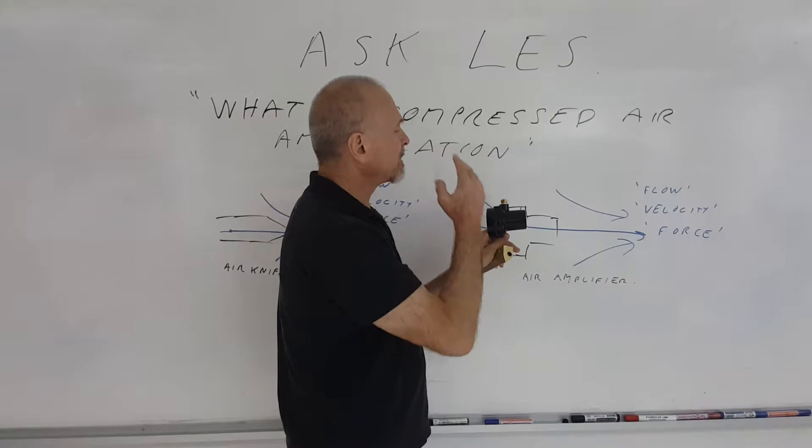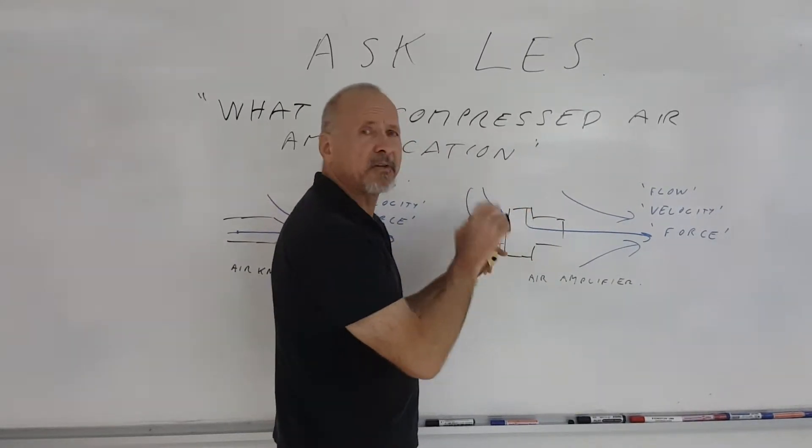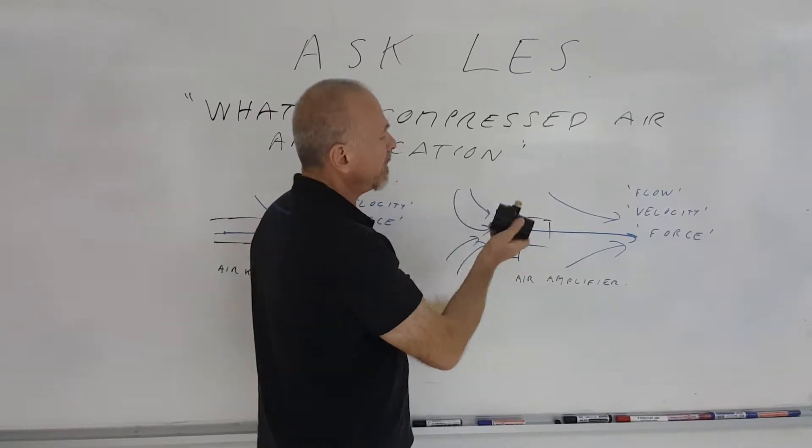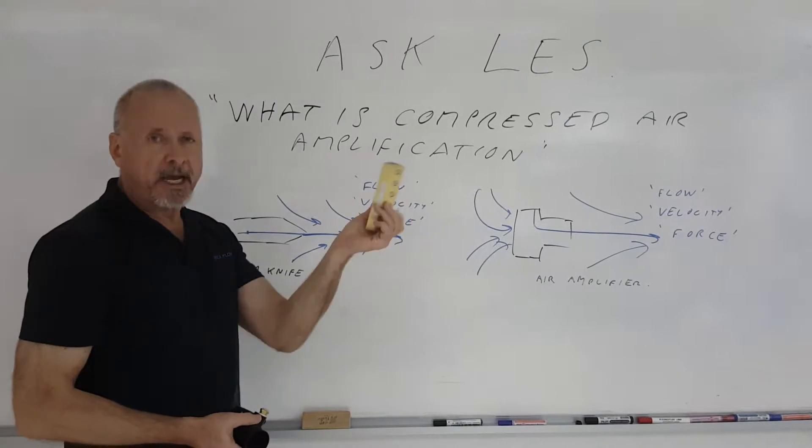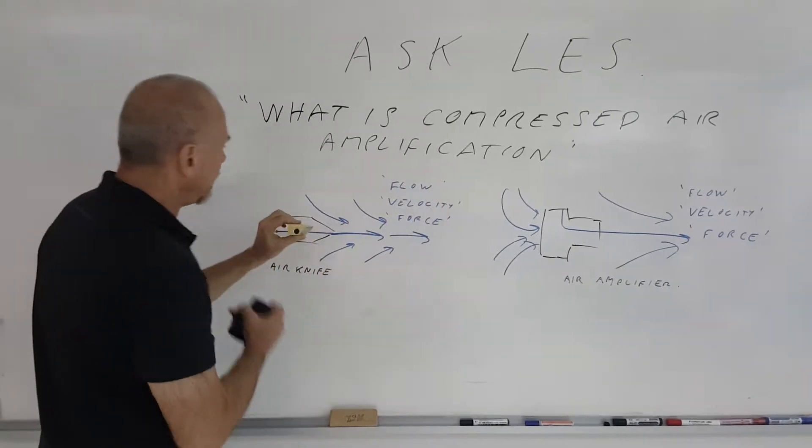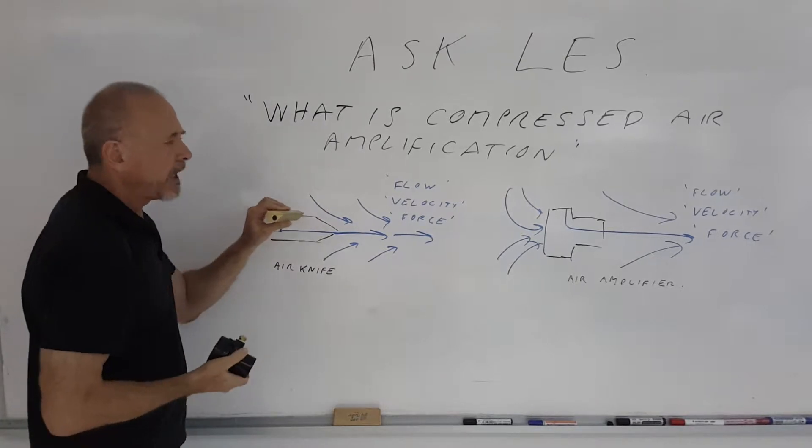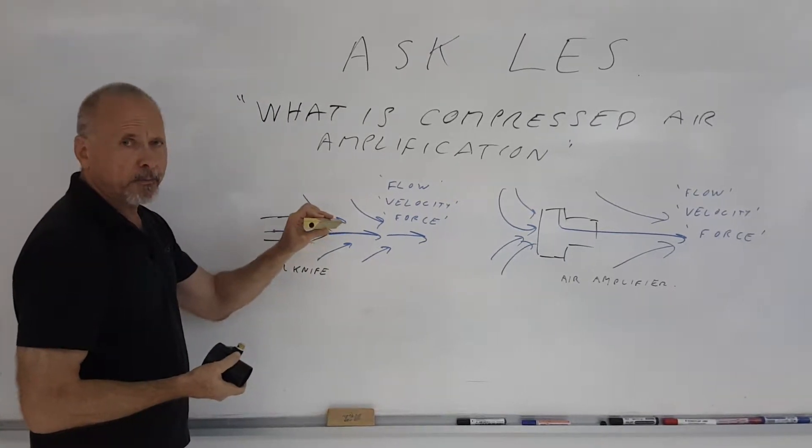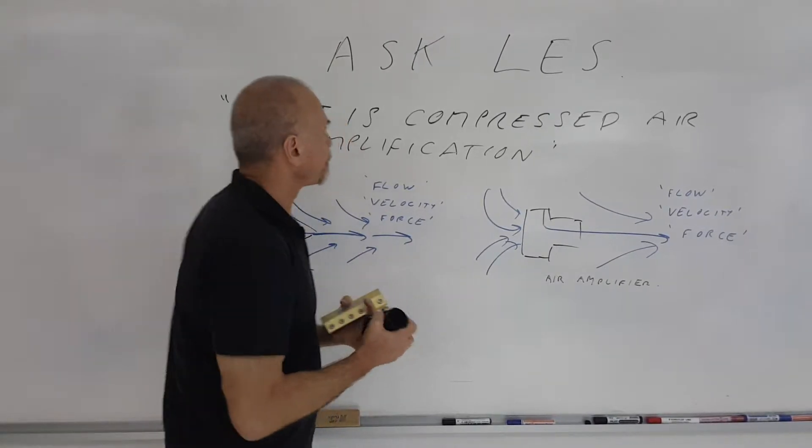What you're really doing is converting pressure that is normally lost as pressure drop and noise into flow. So it's really an energy converter. Quite often amplifiers are actually called air movers. Same thing with an air knife that I have in my hand. The air knife does the same thing - it entrains the air from the atmosphere, amplifying the airflow. Air nozzles work the same way.